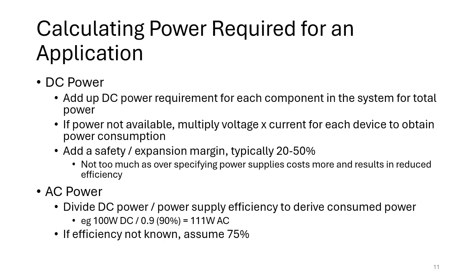So you might need to look at how much overload capacity your power supply has, because it's common for electronic devices to need 2 times or sometimes even more of that current or power when they first start up. So it might be that your 3 amp system actually takes maybe 4 or 5 amps to power up, in which case that's where you need your 5 amp power supply, unless the power supply was capable of driving more current.